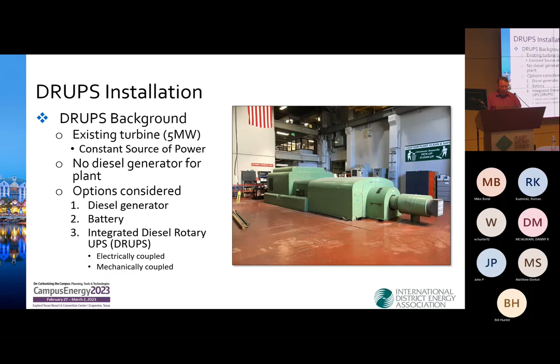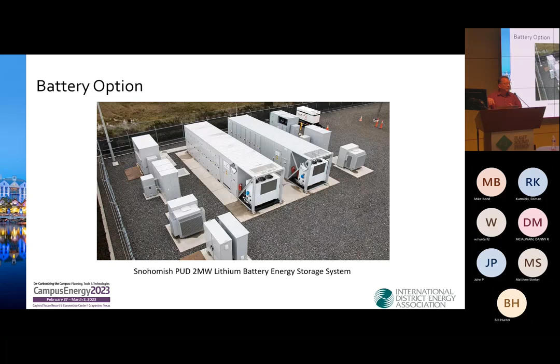But our problem is we had room in the plant. We don't have any room outside of the plant. So putting 2 megawatts worth of battery generation to take the place of our diesel generator while we waited for it to start, it just didn't sit well with anybody. We don't have any room outside, and putting this thing inside just didn't seem the way to go. So we ended up going with the diesel rotary system.